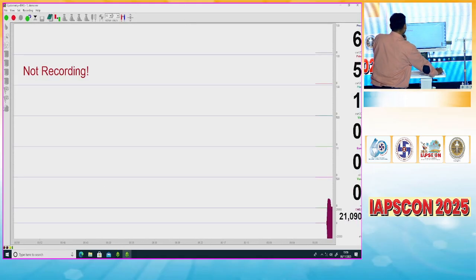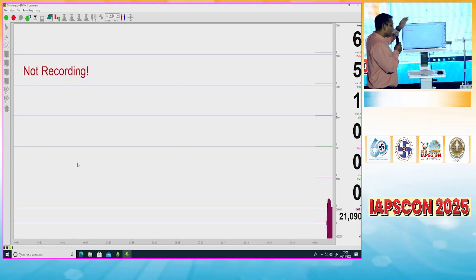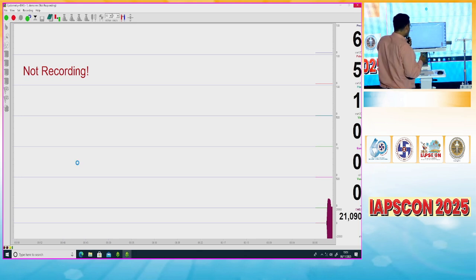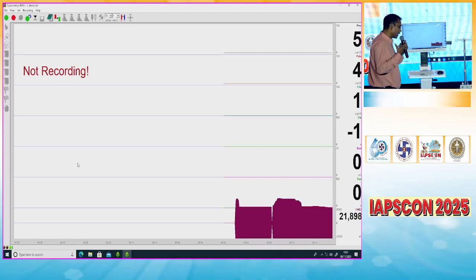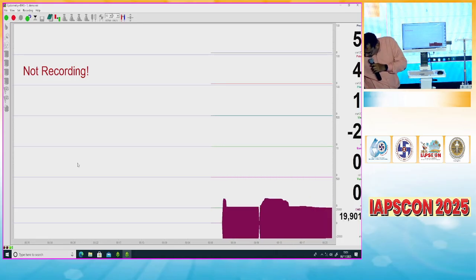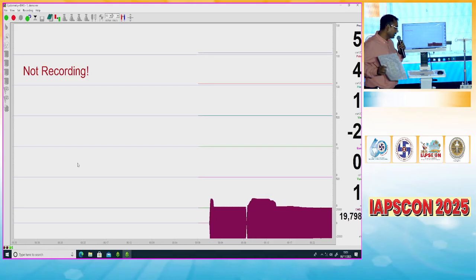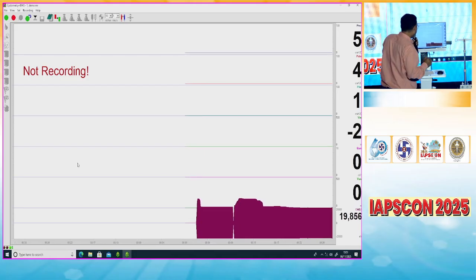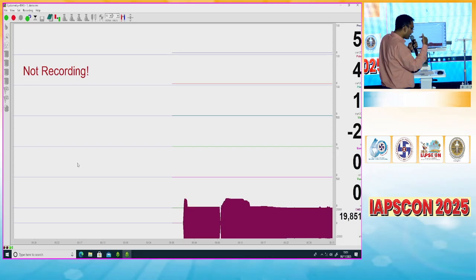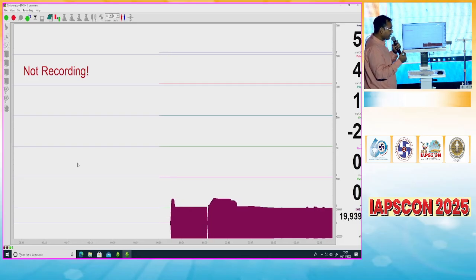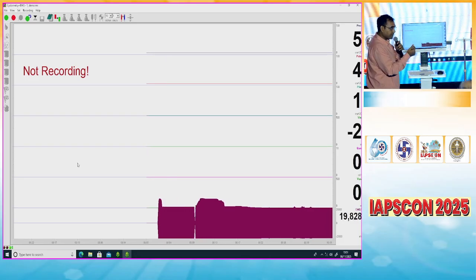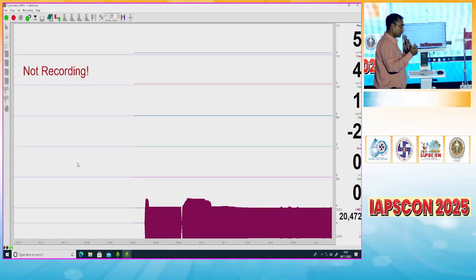So these are the settings which we have created step by step. First, we will do the catheterization of the patient. Then we will do the priming of the transducer and priming of the tubing set. Then it will be connected with the catheter. Then we will attach the tubing with the catheter and we will place the patch electrode EMG on the bladder neck at 3 o'clock and 9 o'clock.